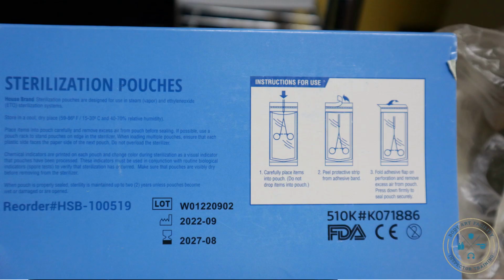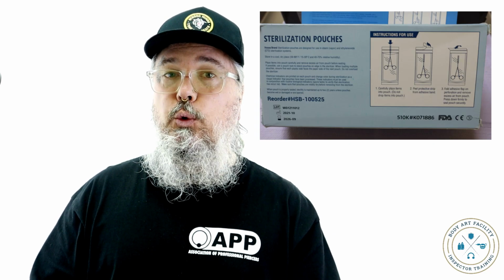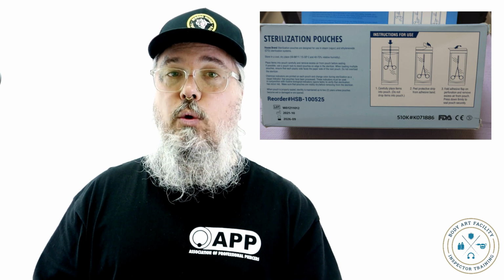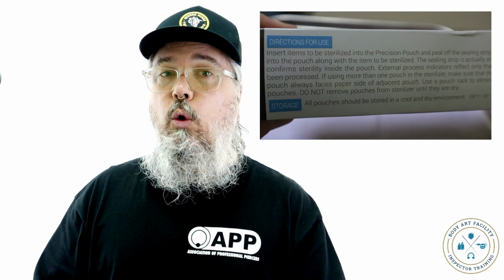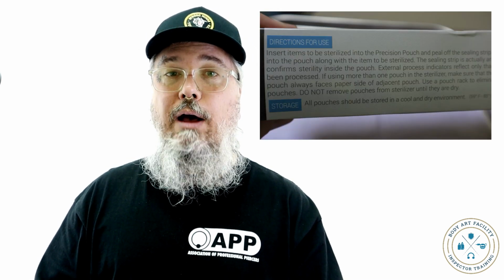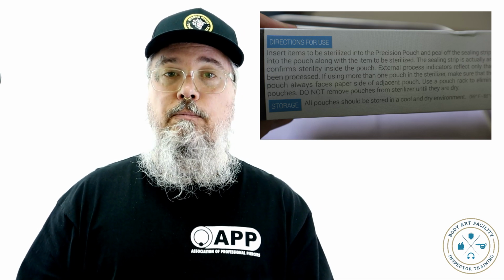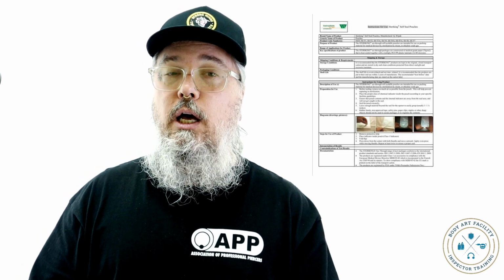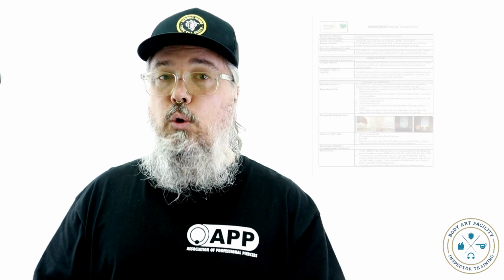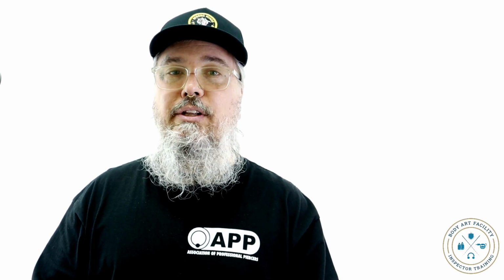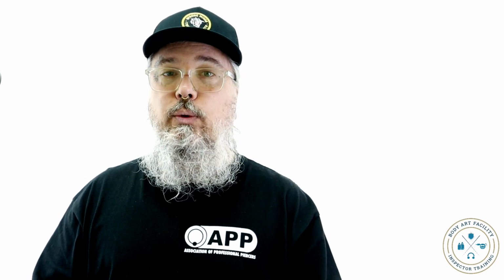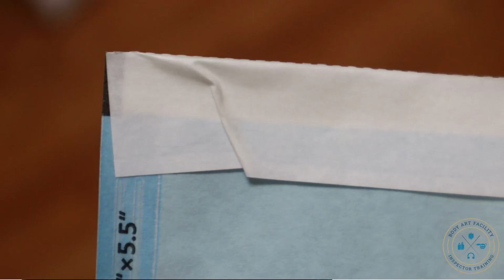The manufacturers of sterilization pouches have instructions for use that need to be observed. For example, a pouch's IFU may require the pouch to be no more than 75% full or have 1 inch of empty space around the contents on all sides. These IFUs can all be found online. Most pouches are self-sealing with an adhesive strip. When using a self-sealing pouch, it's critical that there are no wrinkles in the seal.